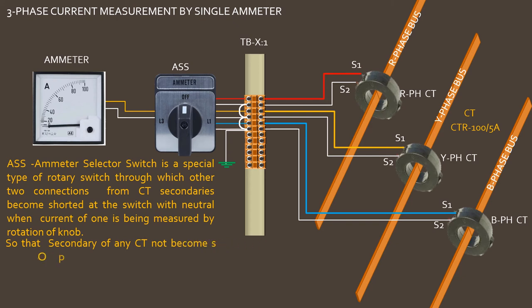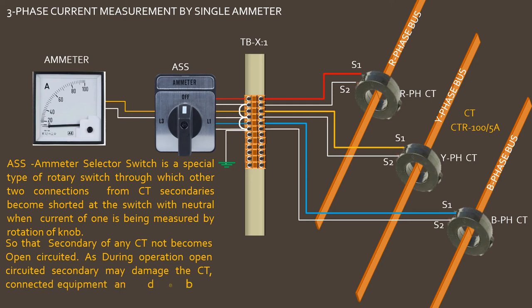With neutral, when current of one line is being measured by rotation of knob of the selector switch, so that secondary of any CT does not become open circuited. As during operation, open circuited secondary may damage the CT, connected equipment, and may be very dangerous to the operator.